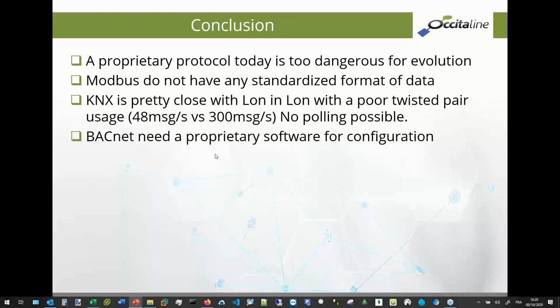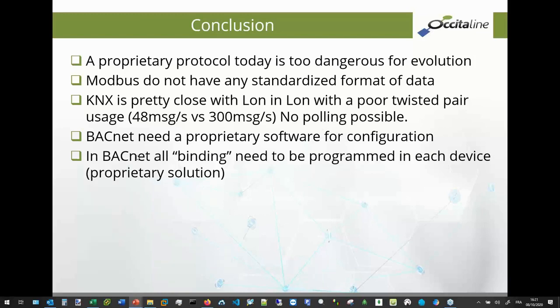KNX is pretty close to LON, with the functional blocks and the different things. But on the same twisted pair, you can't manage more than 48 messages per second versus 300 messages per second in LON. And polling is impossible. You can't poll. In KNX you need a sniffer and an infrastructure device following and memorizing every message on the twisted pair.